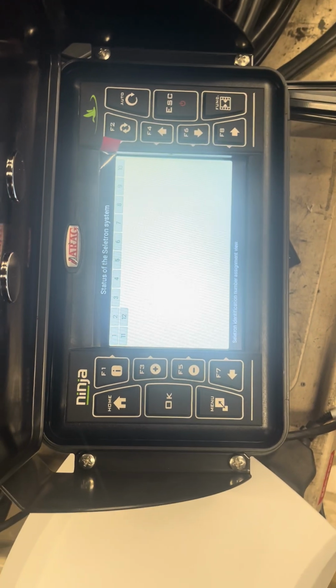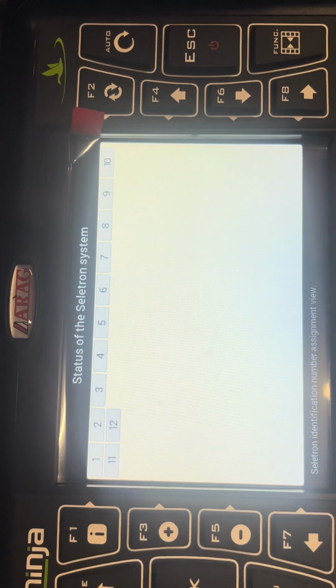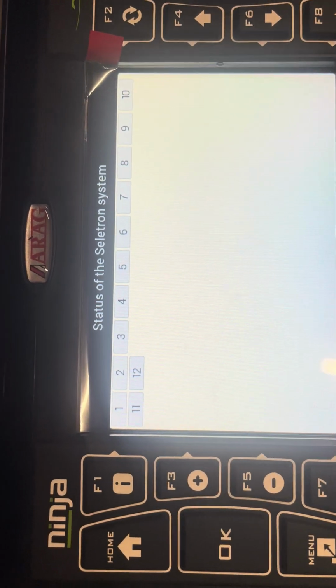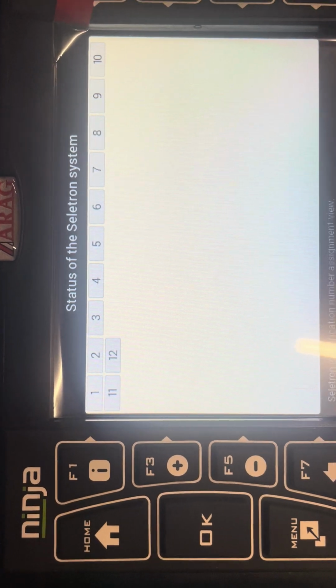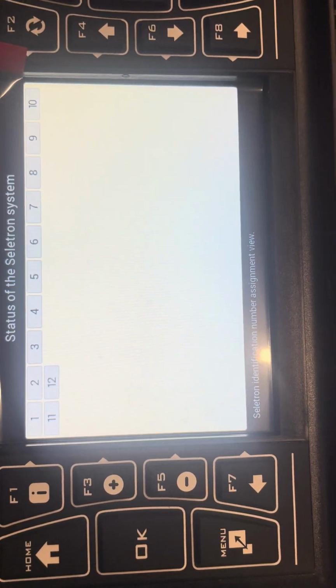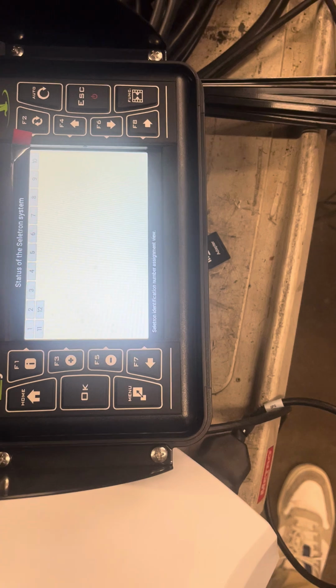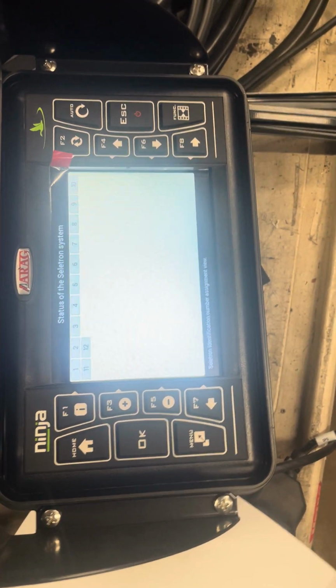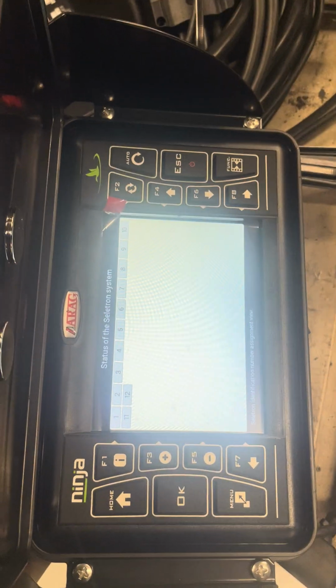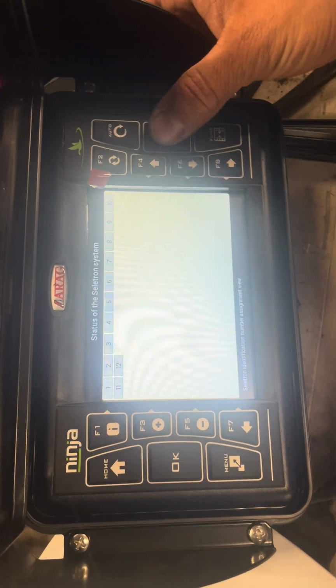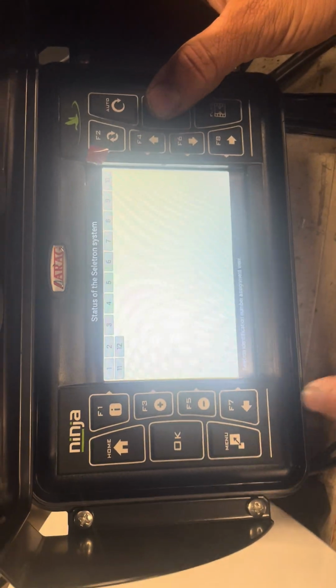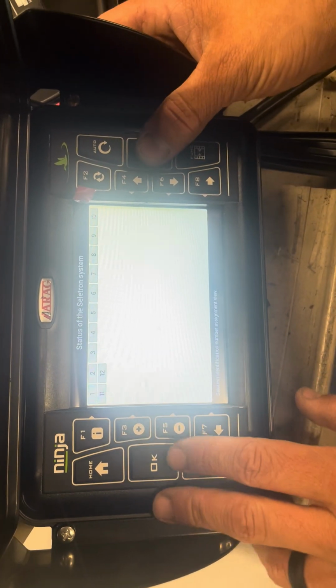Because the ID is on the board in the Seletron, not in the CAN line. The only other way around that is to run an individual signal onto the CAN line, which is 12 more wires, or if you had a 120-foot boom, like 80 positions, it's a pain. But the ID on the board makes it easy. You just have to run through this process.